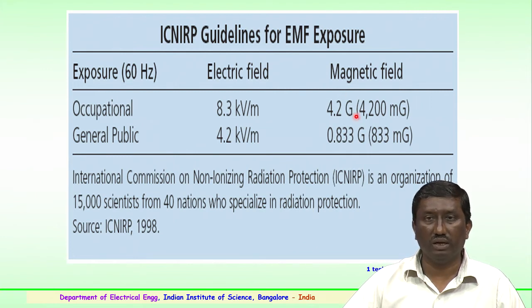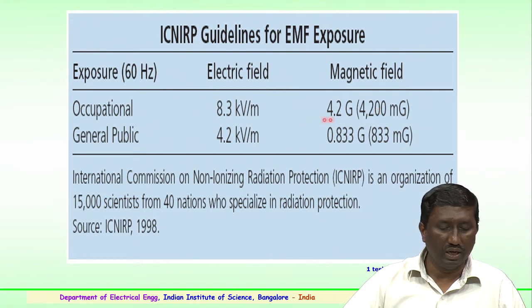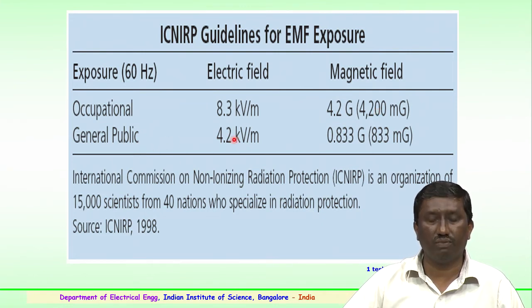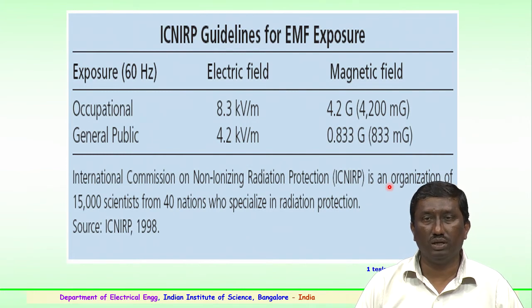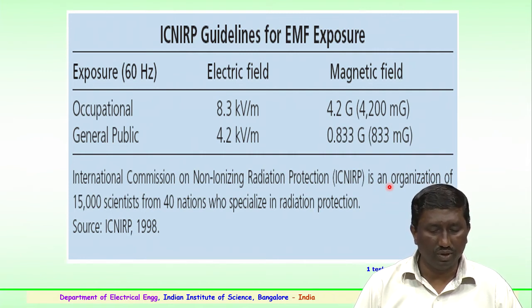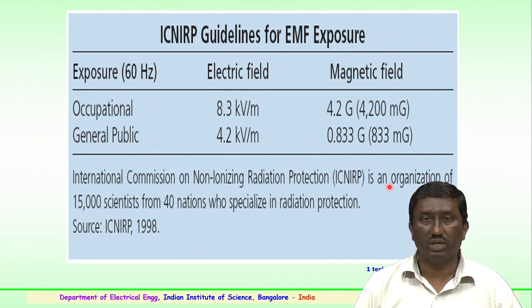And in case of magnetic field, the maximum exposure should not be more than 4.2, or 4200 milligauss. This is the value. And in case of the general public, the electric field should not exceed 4.2 kilovolt per meter, or 0.833 gauss, or 833 milligauss.